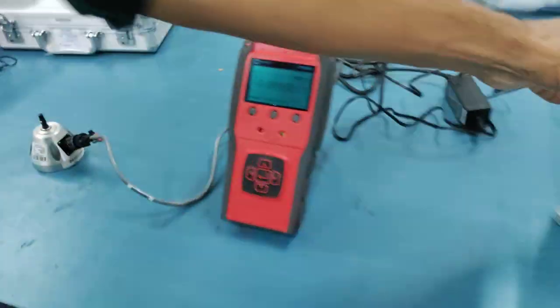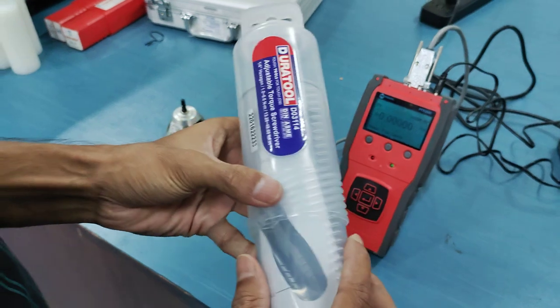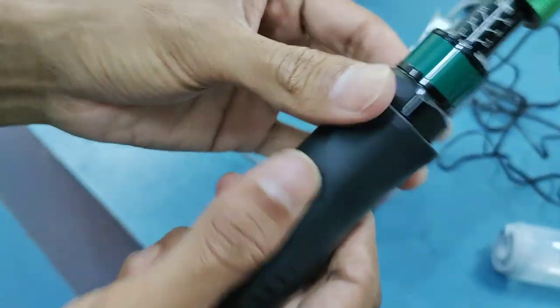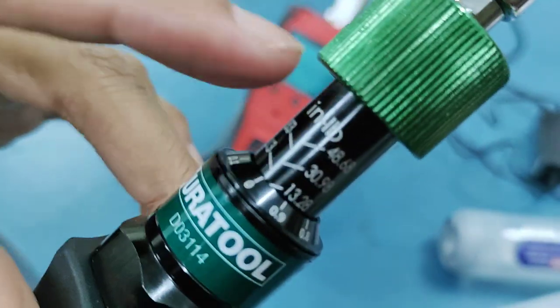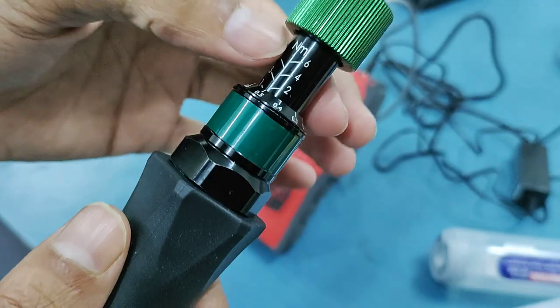Now I'll be showing how to set the value in the torque screwdriver and then test it with the reader. This is a Duratool adjustable torque screwdriver with a range of one to six Newton meters. You will get two kinds of readings: one is in Newton meters and the other will be in inch-pounds. For the testing purpose, we'll be using Newton meter units.